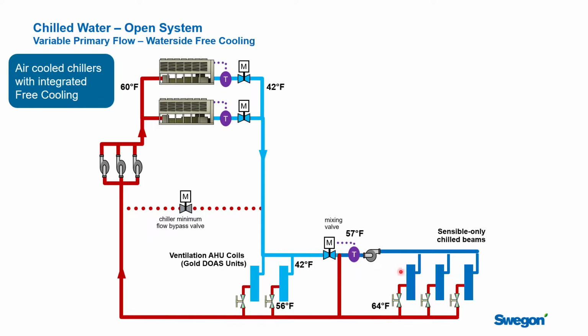Now, these chill beams are going to see a cooling load even in the winter. If you're in the core of the building, in a large building, even in a cold weather climate, we're still going to have sensible heat gains in the space that we have to manage. And so we need a source of 57 degree water, even though it's cold outside. We would love to shut down the chiller plant and find a way to do that with free cooling.